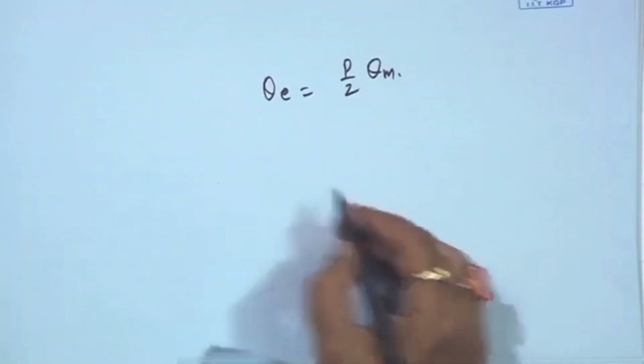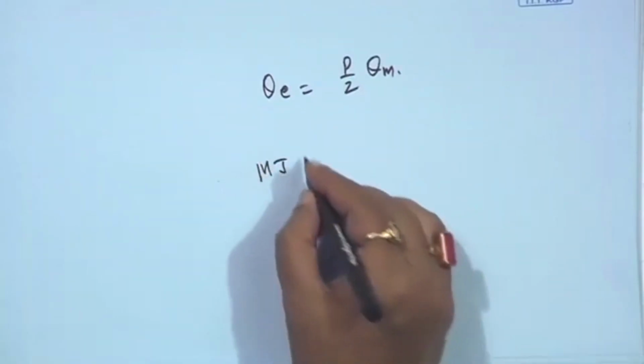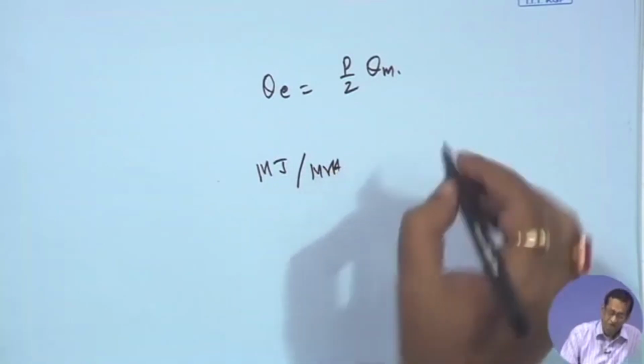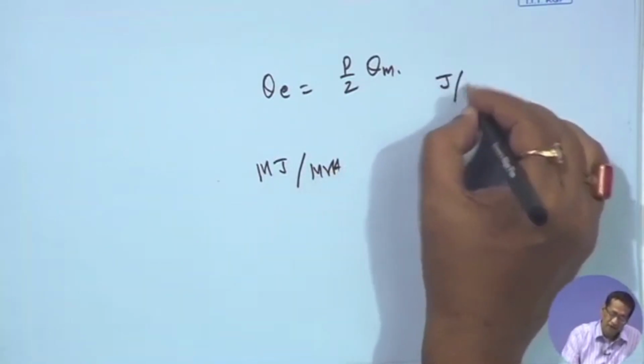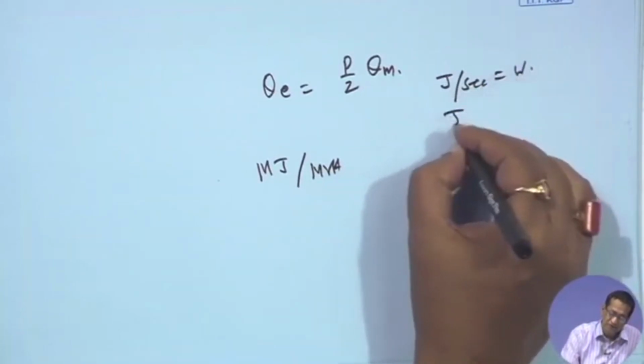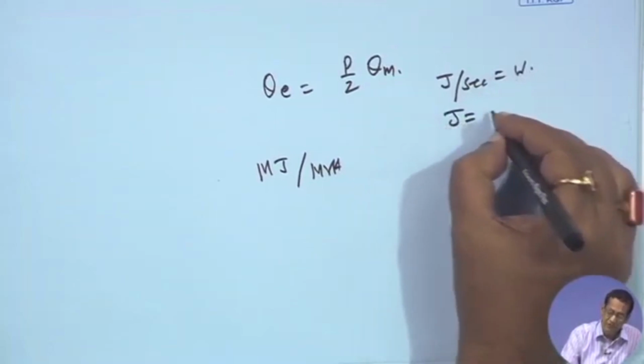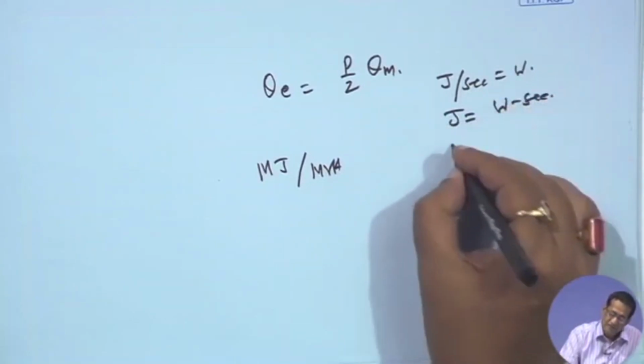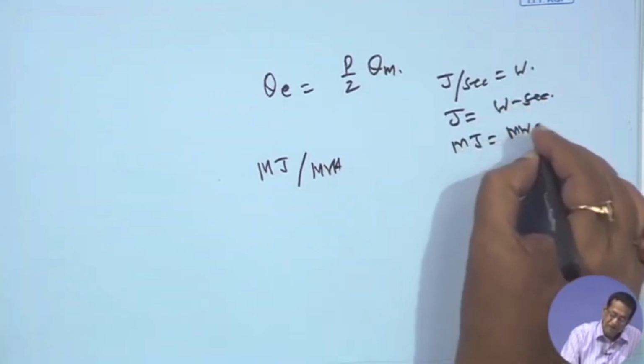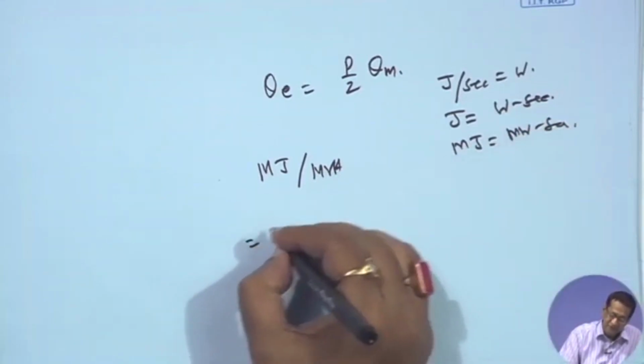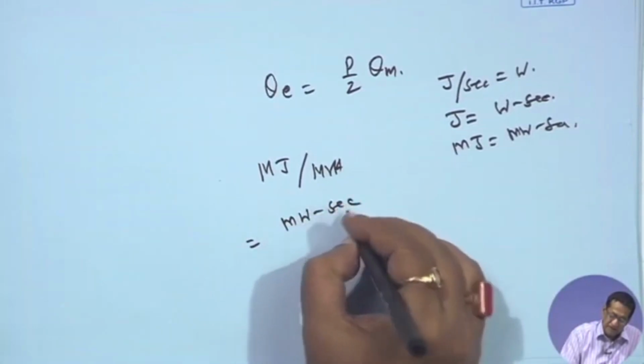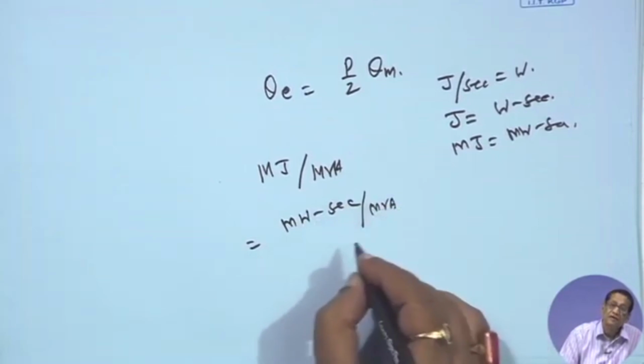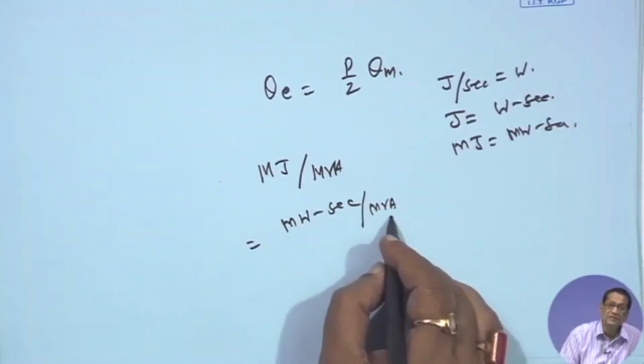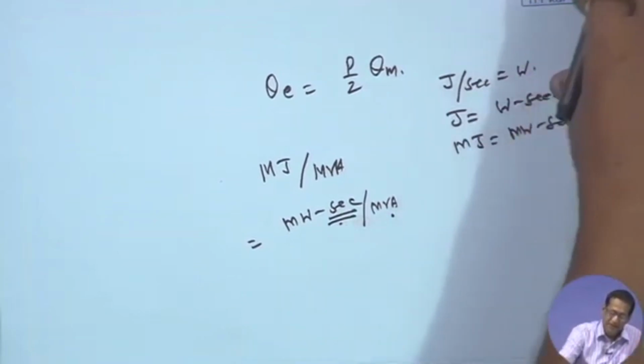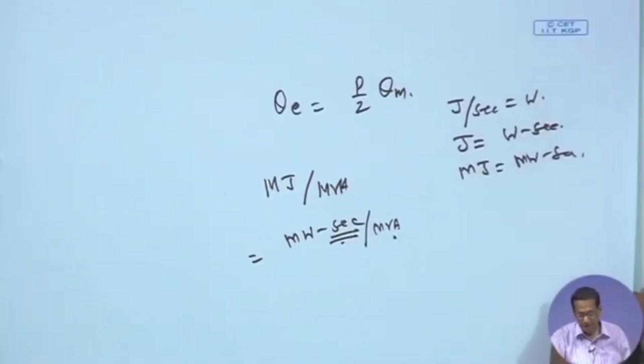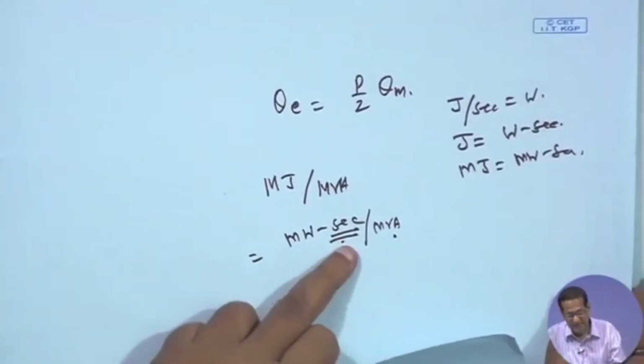If it is megajoule per MVA: since joule per second equals watt, joule equals watt-second, so megajoule equals megawatt-second. That means this can be written as megawatt-second per MVA. So MVA, megawatt by MVA, is a dimensionless quantity, meaning H can be defined in seconds also. So if you read some books, you will find the inertia constant H given in seconds, but actually it is megawatt-second per MVA.